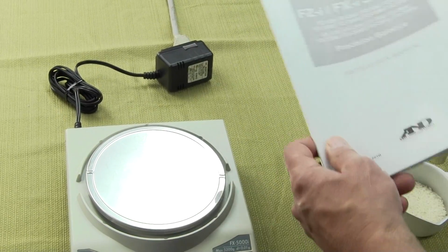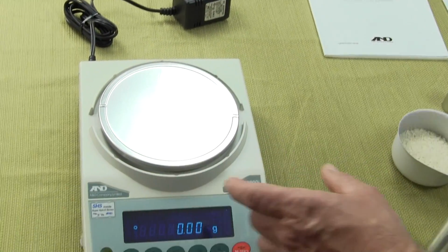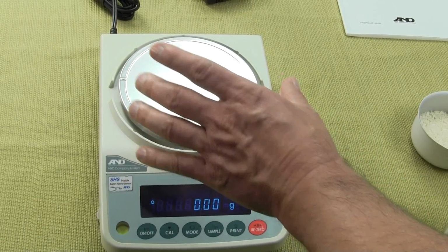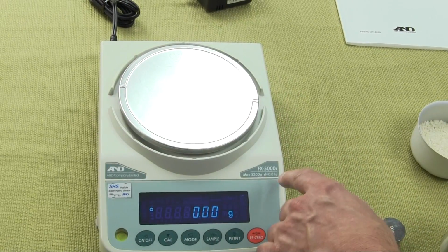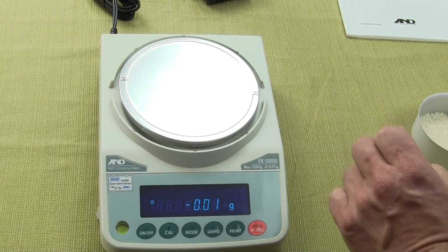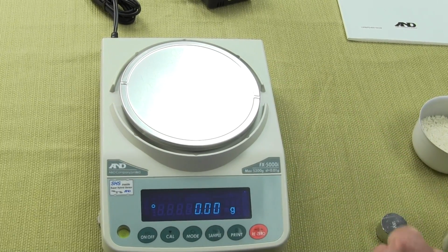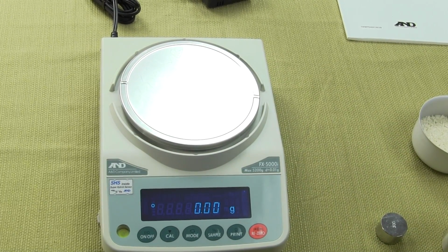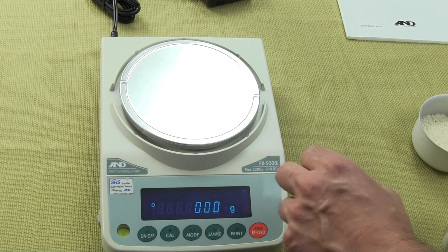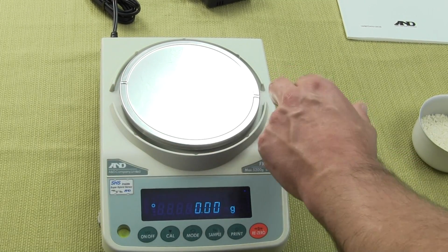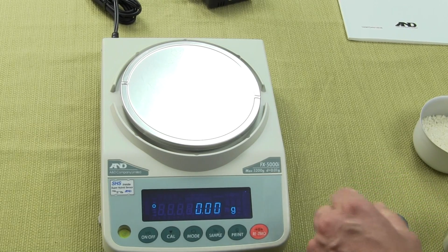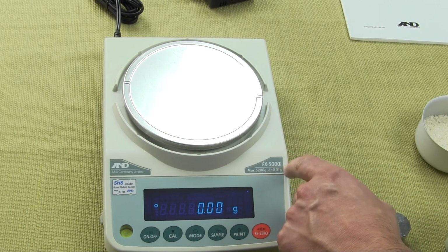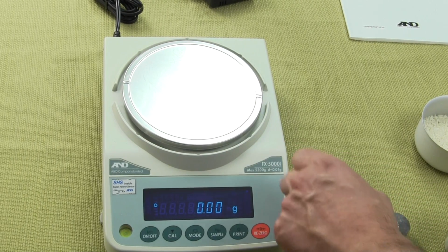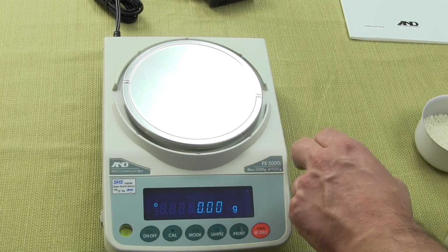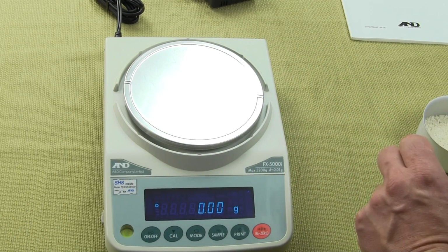We've already covered the milligram balances having the draft shield. The 0.01 balances do have the larger weigh pan - that's one nice feature with this. On this particular balance, your weigh pan diameter is 5.9 inches, versus on the 0.001 readability balances, the 1 milligram balances, that diameter is 5.7 inches.